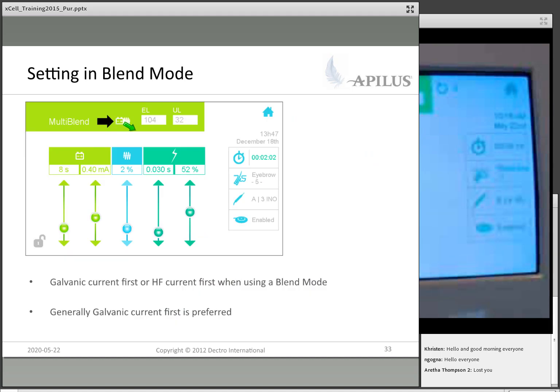So the lead, we didn't talk about the lead here. The lead is kind of interesting, as in it is to decide which current I want to turn on first when I press on the foot pedal. Factory preset means that the lead will be the galvanic, which is the battery, first, and then the high frequency second. I can change this.